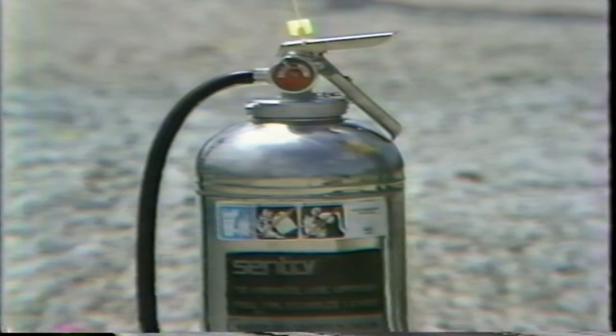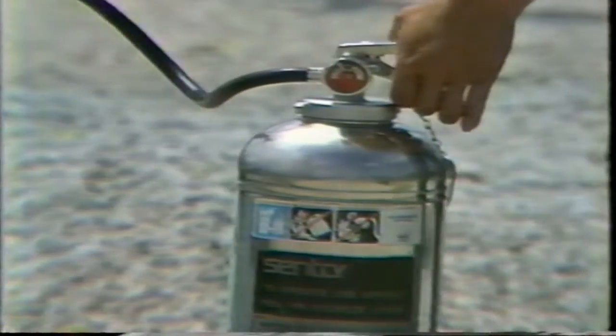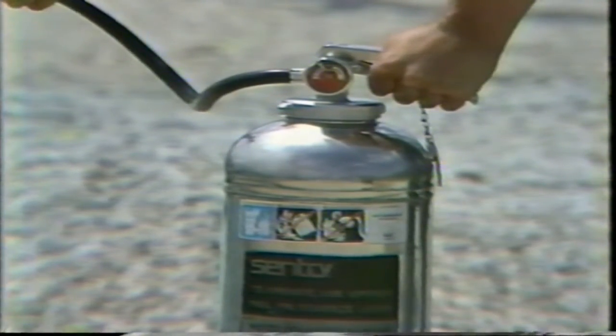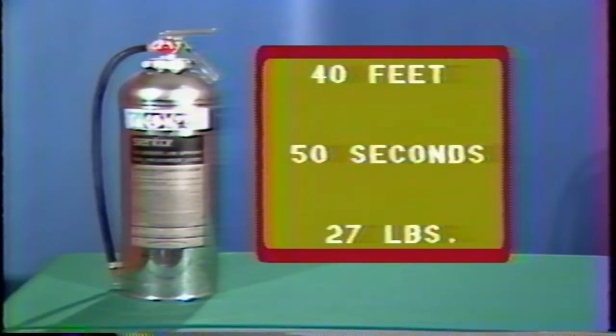To operate the unit, pull the ring pin. Grasp the nozzle and direct it at the base of the burning material. Squeeze the operating lever. This extinguisher carries a rating of 2A, meaning it is capable of extinguishing about 12 pounds of excelsior spread out in layers 4 feet wide and 8 feet long. It has a range of 40 feet and an effective discharge time of 50 seconds. Total weight of the unit is 27 pounds.